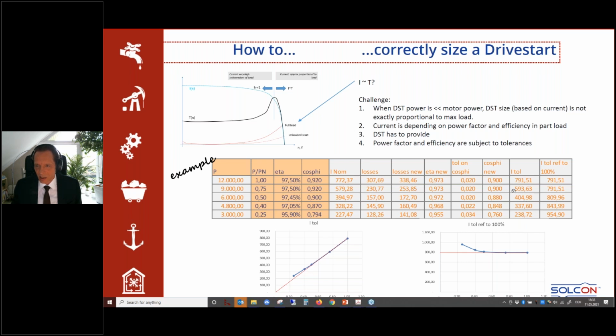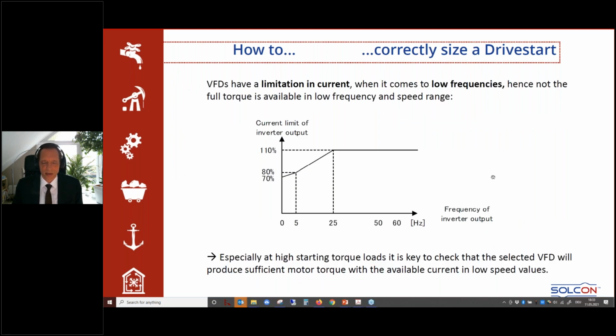Okay. The tolerance value is 238 amps, and this is the value which I have to minimum achieve with a drive start. If I had chosen this value, I would be wrong by 10 amps. It can make a difference. Secondly, the second challenge is that a VFD type starter cannot produce the full torque and the full current at zero frequency. Here you have a limitation that the drive start or any VFD starter can produce only 70% of the starting current of its nominal current. And in case you have, let's say, a high starting load, like for instance a ball mill, you have to take great care to correctly size the drive start so that you develop enough current, and with it, with what I have said before, also enough torque. So this you have to consider when sizing a drive start, but once you are doing this, you have done the right thing.